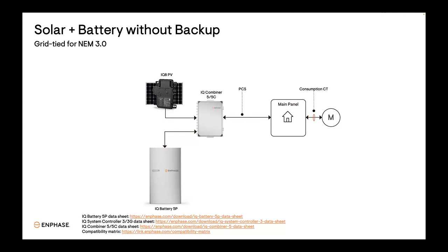So this is designed to be a very simple system from Enphase. As you can see, the IQ Battery 5P can be connected directly into the IQ combiner instead of into the main panel or the controller. So that's going to save on labor and materials. There's no backup loads panel, and no circuits need to be moved from the main panel into a backup loads panel because it's not a backup system. You also don't have the IQ system controller in this configuration, obviously, because it's not a backup system. So these systems are designed to be as low cost as possible so the customer can get the financial benefits of having a battery without paying the additional costs required for a backup power system.